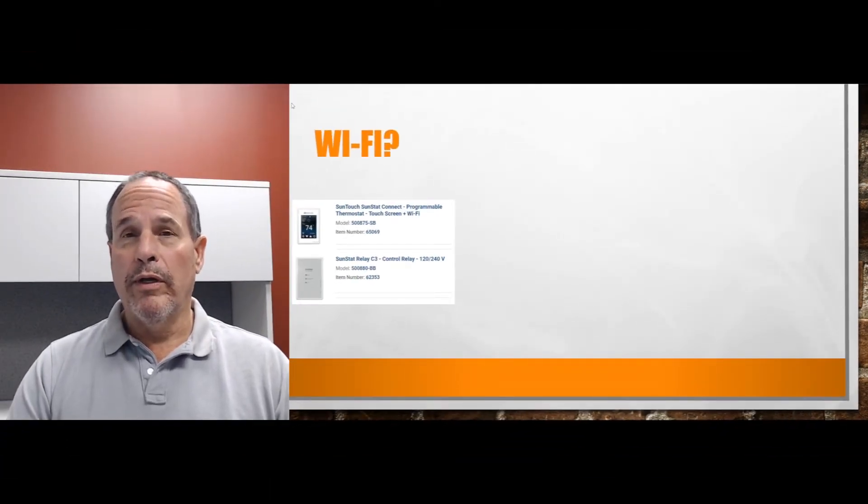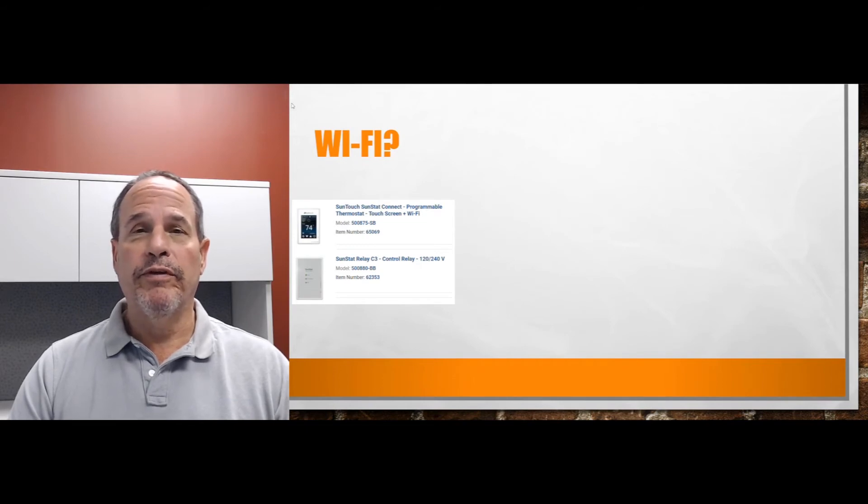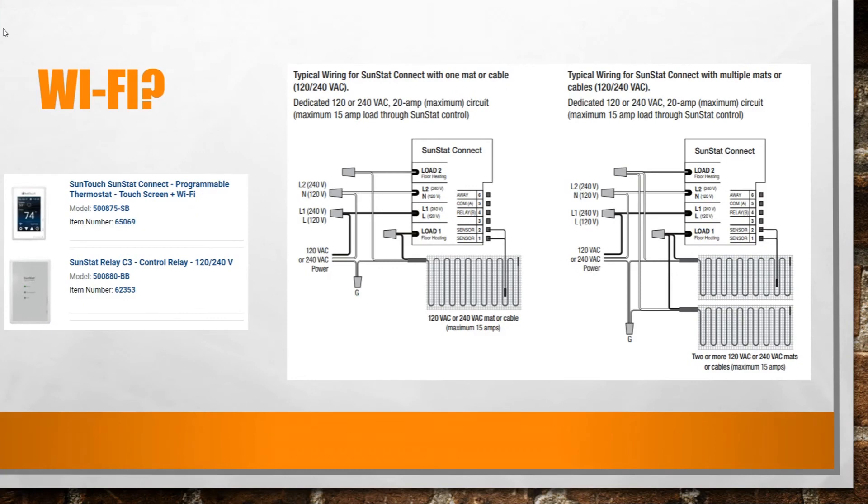As I say, that one thermostat will handle up to 15 amps, so if you have a couple of baseboard heaters that add up to 15 amps, then you could use that one thermostat for both.